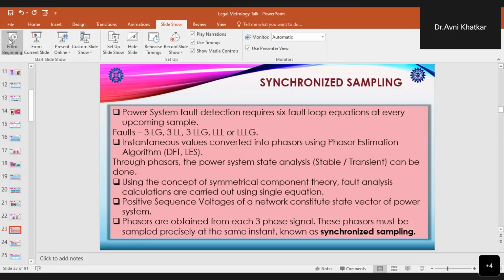And by having this synchronized sampling, we get synchrophasors. Synchrophasors are nothing but the phasors which represent the fundamental of an AC signal, whose magnitude is the RMS value of the fundamental amplitude, and the angle is the difference between the signal fundamental angle and the phase angle of the cosine at the nominal signal frequency, which is synchronized to the UTC time.